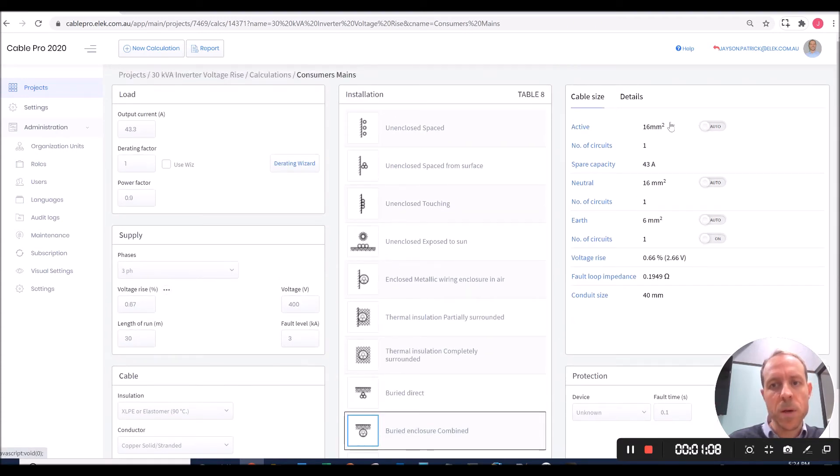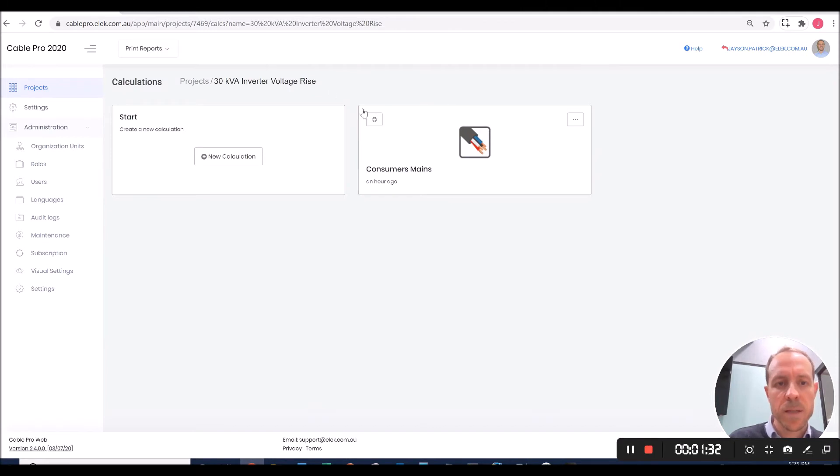CablePro determines a minimum required cable size of 16 square millimeters, which is smaller than the hand calculation of 25 square millimeters. That's because we use the very accurate voltage drop calculation method. Here's the actual voltage drop in percent. We'll go back to the project and perform the same calculation for the final sub-circuit.